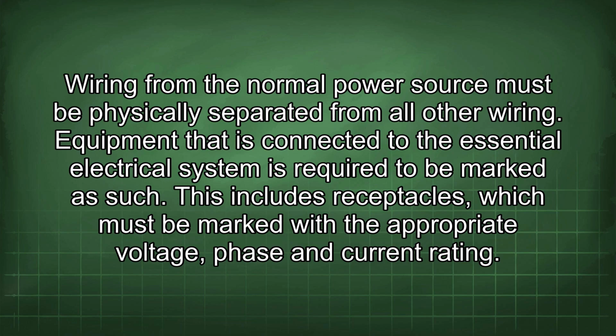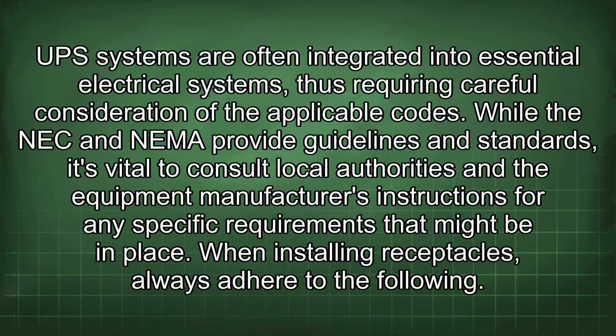Equipment that is connected to the essential electrical system is required to be marked as such. This includes receptacles, which must be marked with the appropriate voltage, phase and current rating. UPS systems are often integrated into essential electrical systems, thus requiring careful consideration of the applicable codes. While the NEC and NEMA provide guidelines and standards, it's vital to consult local authorities and the equipment manufacturer's instructions for any specific requirements that might be in place.